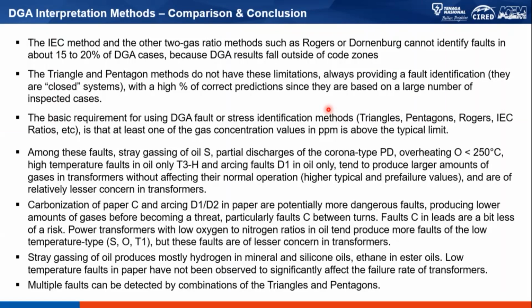I advise you perhaps you should go for OQA or FURAN, for example, because in terms of accuracy, sometimes less than this 10 or 15 ppm could generate some kind of error. And based on IEC, the accuracy should be more than 30% before you can use the DGA method to interpret the results. So the basic requirement for using DGA, as I mentioned just now, is that at least one of the gas concentration values in ppm is above the typical limit.